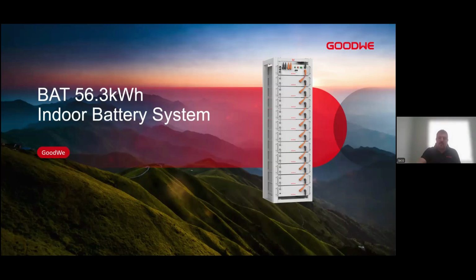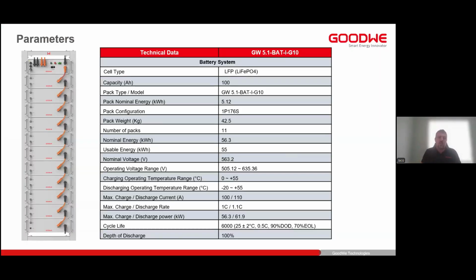Then, as a separate offering for more cost-effective applications, we also have a rack-mount battery solution. The rack-mount battery system is a 56 kilowatt hour battery bank. This unit also has built-in fire suppression, but will require external active cooling. The pack nominal energy is 5.12 kilowatt hours, and that will allow for easy assembly on site. It is a 1.1C rated battery, and it also has a 6,000 cycle life. So being a 1.1C battery, it means that we can have a 56 kilowatt hour bank connected to a 50 kilowatt inverter, which then as a total solution is extremely cost effective.